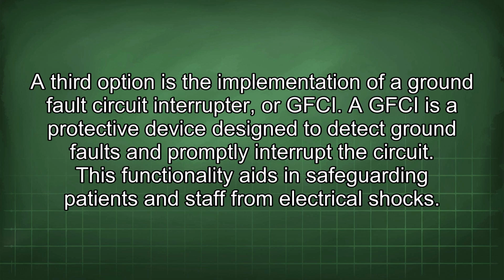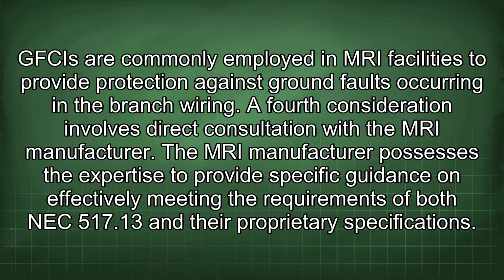A GFCI is a protective device designed to detect ground faults and promptly interrupt the circuit. This functionality aids in safeguarding patients and staff from electrical shocks. GFCIs are commonly employed in MRI facilities to provide protection against ground faults occurring in the branch wiring. A fourth consideration involves direct consultation with the MRI manufacturer. The MRI manufacturer possesses the expertise to provide specific guidance on effectively meeting the requirements of both NEC 517.13 and their proprietary specifications.